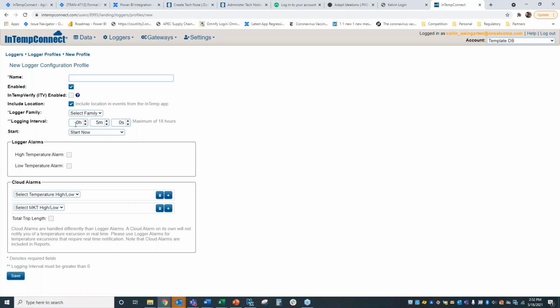You can go down to 1 second, although I really don't recommend that because you run out of memory very quickly. You can go up to 18 hours. You can define how the logger starts, so you can have it start immediately or after elapsed time, which is mostly used by logistics and transportation customers. They'll say don't start until maybe an hour later, so it gives them time to condition the loggers in maybe a cold room or something, so there isn't false alarms at the beginning of the shipment.